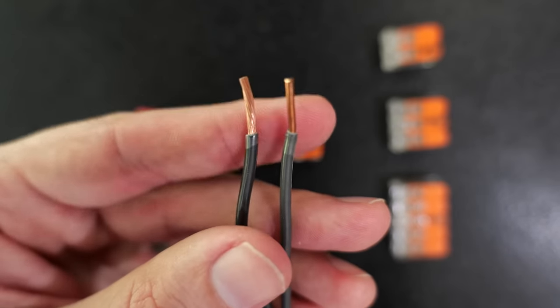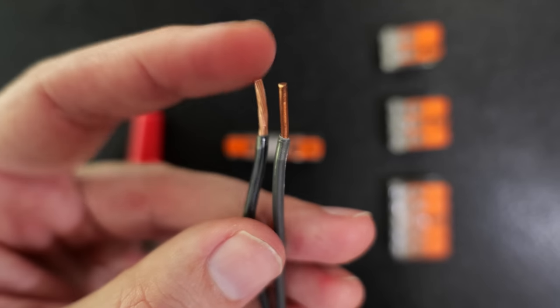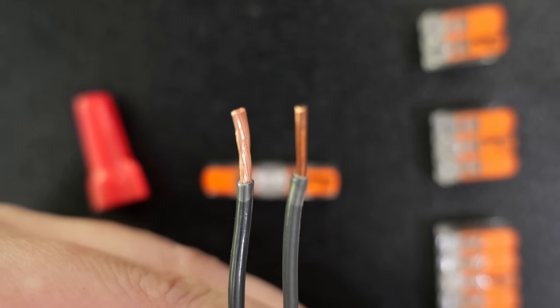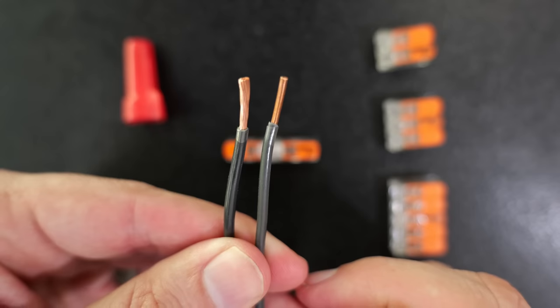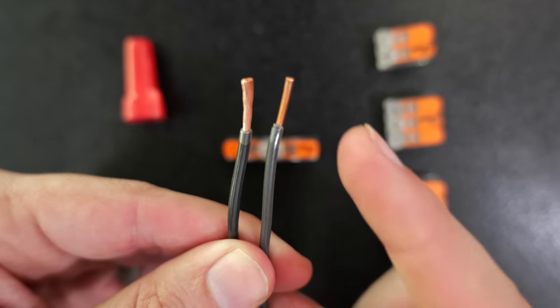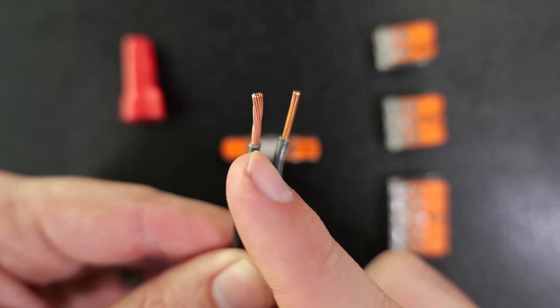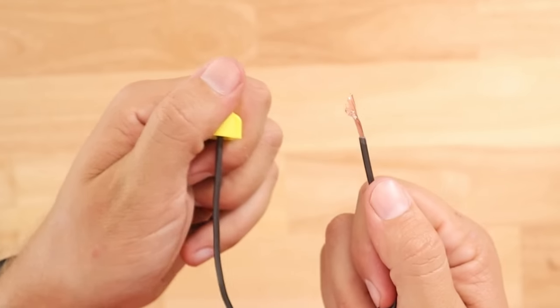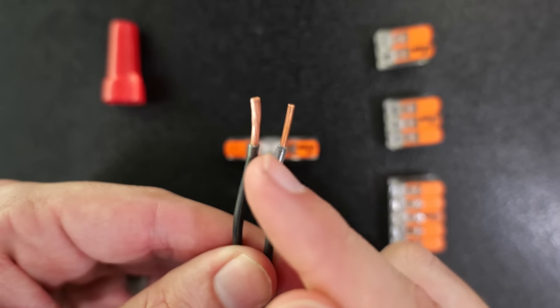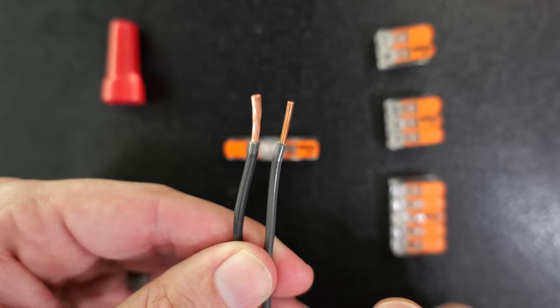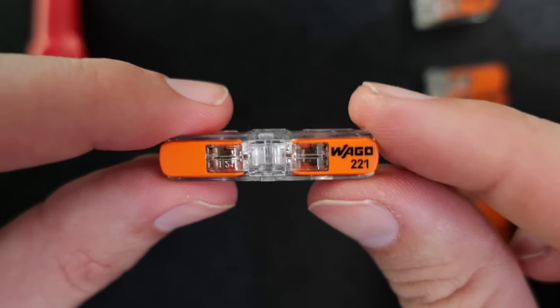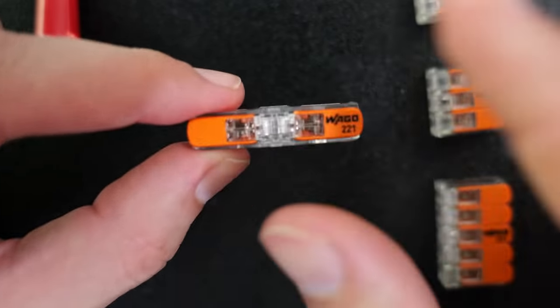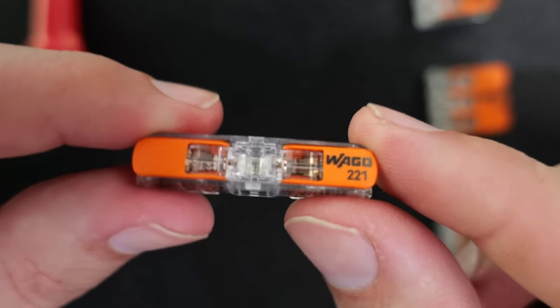Another area where the WAGOs can come in handy is when we need to make a connection between stranded to solid core. And regardless of skill level and experience, it could be argued that this is one of the most difficult connections to make. The reason for that is when you go to connect stranded to solid core, a lot of times the stranded might not bite as well underneath one of these wire nuts as the solid core will. So if these two wires are not connected together properly, it's more prone to fail.